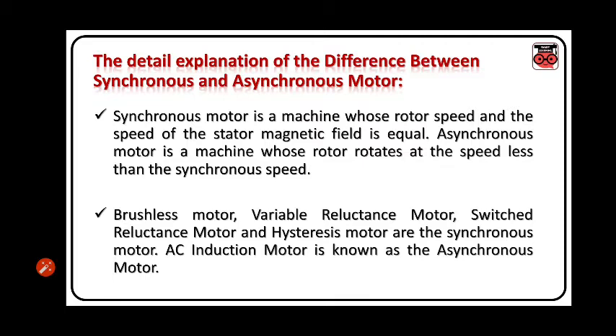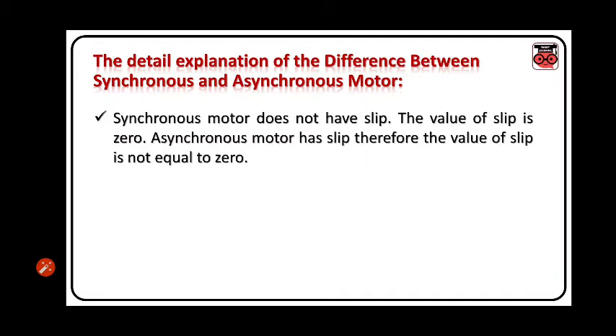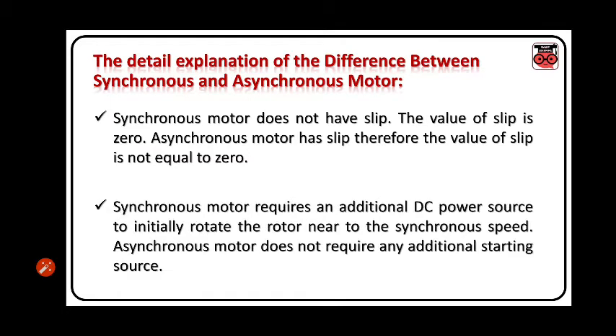Brushless motor, variable reluctance motor, switched reluctance motor, and hysteresis motor are synchronous motors. Synchronous motor does not have a slip — the value of slip is zero — whereas asynchronous motor has a slip, so the value of slip is not equal to zero. Synchronous motor requires an additional DC power source to initially rotate the rotor near to the synchronous speed, whereas asynchronous motor does not require any additional starting source.